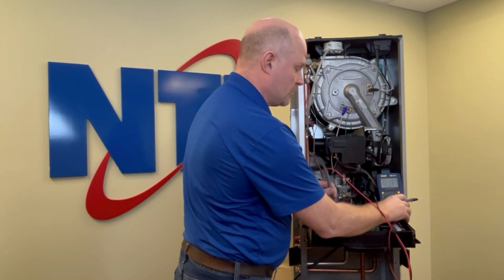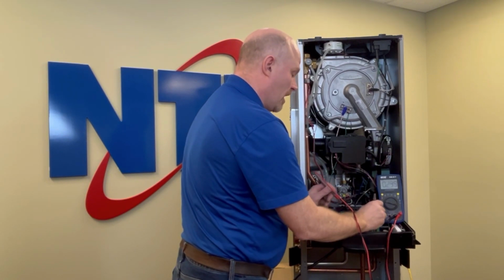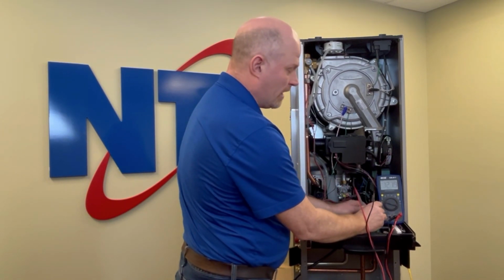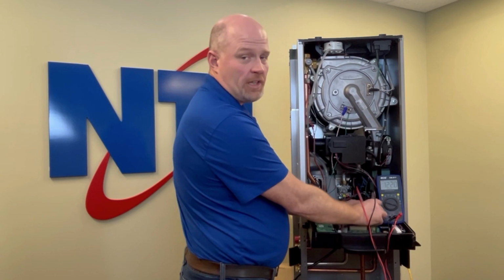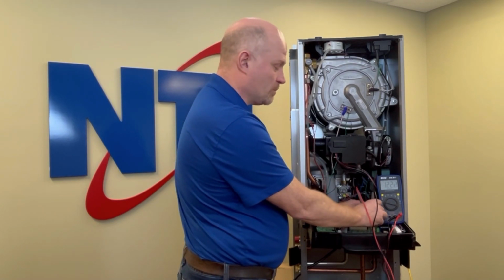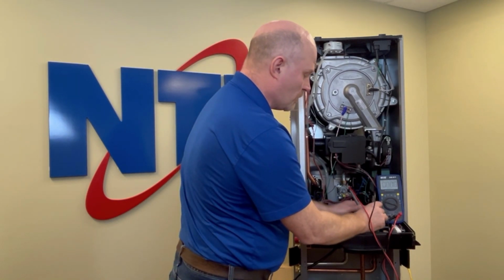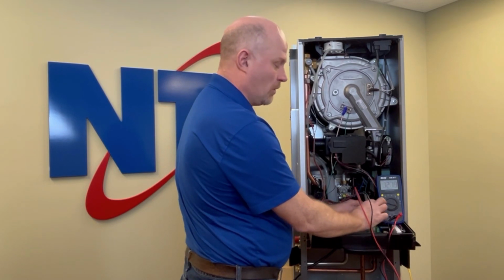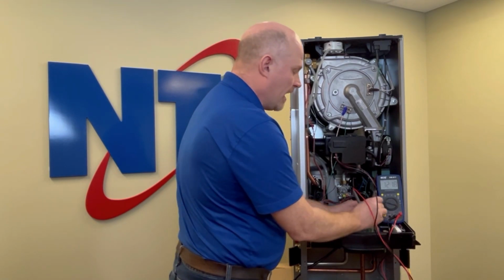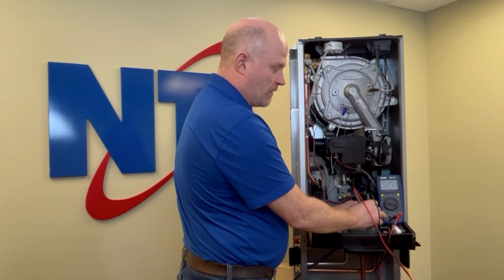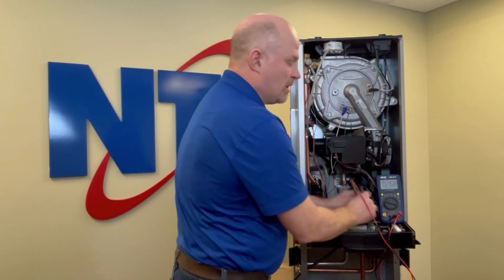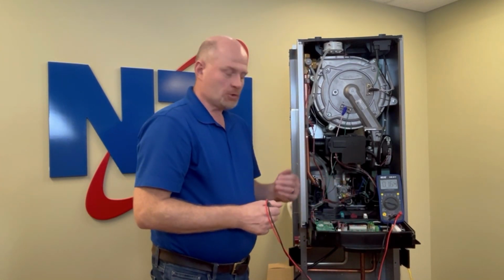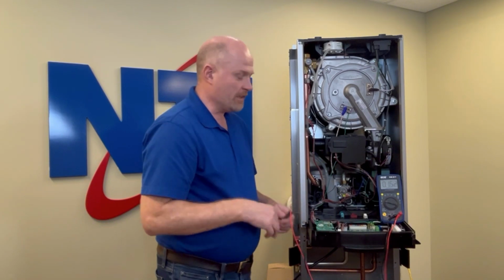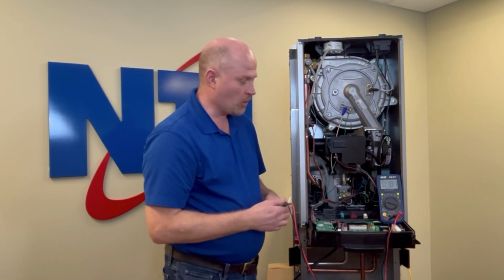The standard voltage check is to go from line to neutral. You should get approximately 120 volts plus or minus 5 or 6%. You want to go from line to ground. You should also have 120 volts. And lastly, go from neutral to ground. If you see more than 1 or 2 volts on your neutral to ground connection, it indicates that there is an open neutral in the system and that you need to trace your wiring and ensure that all the wire nuts are tight and the switches are connected properly.